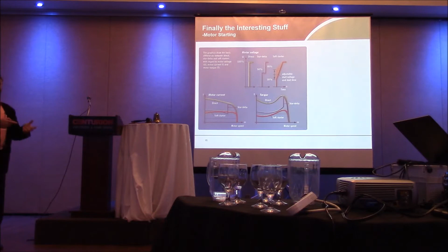Now, the huge inrush current in a properly sized electrical distribution system is not a problem when you're connected to the utility, because the utility grid has Niagara Falls, Chats Dam, the 100-some-odd megawatts that are generated in the middle of the Ottawa River here, big nuclear plants, wind farms, solar farms. We generate terawatts of electricity. But a generator is one little internal combustion engine typically hooked to an alternator. So if I've got a 500 horsepower engine driving a generator, I can't start a 300 horsepower electric motor.